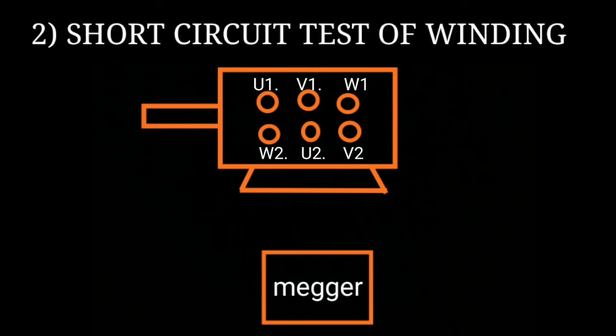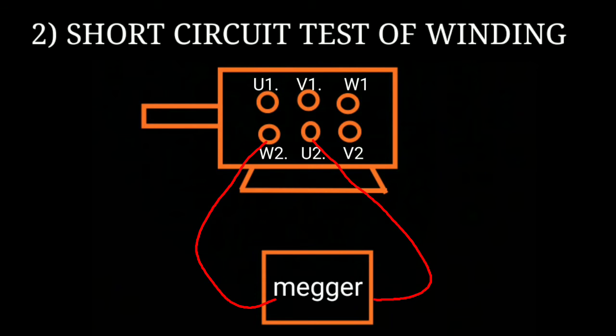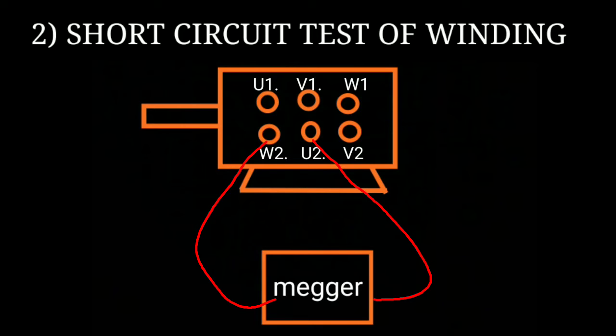Our second test is the short circuit test of winding. Your megger probe is connected between two different windings. See that W2 and U2. If the megger reading shows zero, that means there's a short circuit between two windings. If the megger reading is infinite, the motor winding is okay. Repeat this process with other windings.